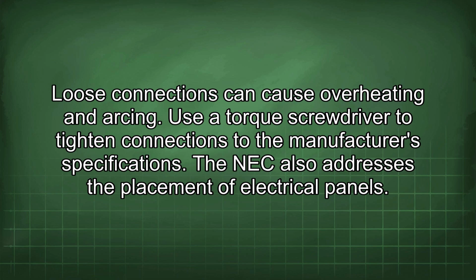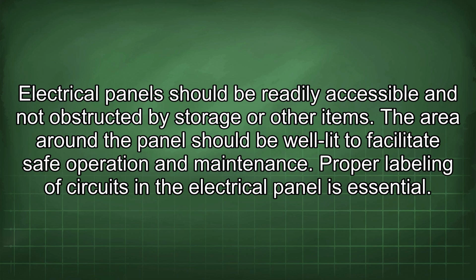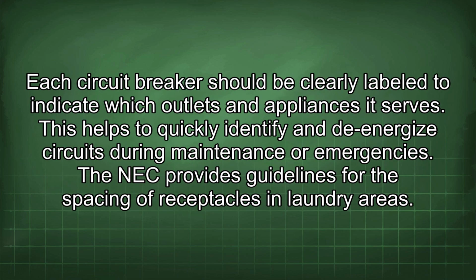The NEC also addresses the placement of electrical panels. Electrical panels should be readily accessible and not obstructed by storage or other items. The area around the panel should be well lit to facilitate safe operation and maintenance. Proper labeling of circuits in the electrical panel is essential. Each circuit breaker should be clearly labeled to indicate which outlets and appliances it serves. This helps to quickly identify and de-energize circuits during maintenance or emergencies.